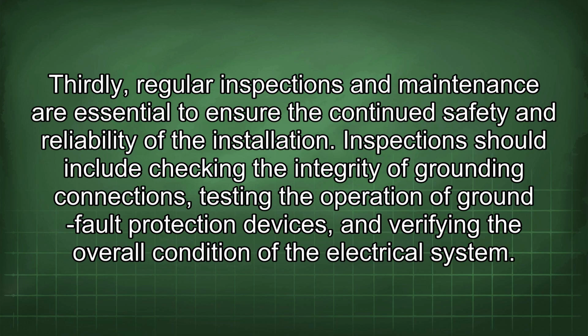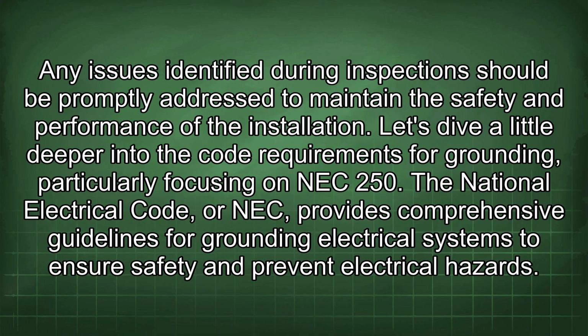Thirdly, regular inspections and maintenance are essential to ensure the continued safety and reliability of the installation. Inspections should include checking the integrity of grounding connections, testing the operation of ground fault protection devices, and verifying the overall condition of the electrical system. Any issues identified during inspection should be promptly addressed to maintain the safety and performance of the installation.